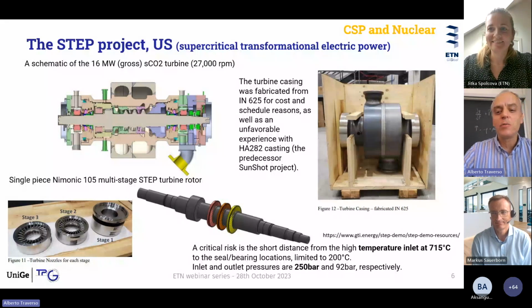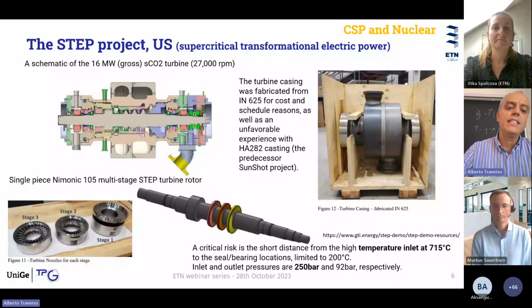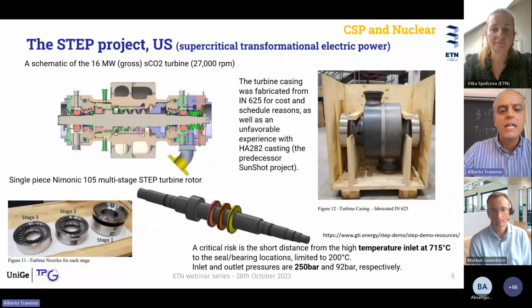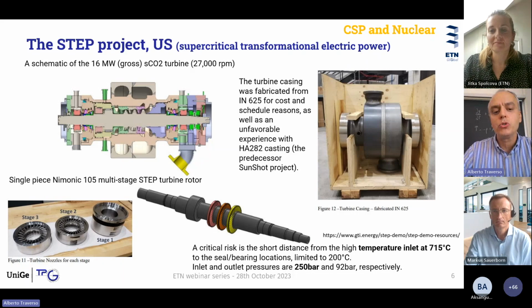Okay, so the STEP project is probably the most prominent one, and is targeting a 10 megawatt net power, but the turbine is actually 16 megawatt. And this comes from the Sunshot program targeting CSP application. If we look at the turbine itself, we find some features that are common also to other turbines, which has a quite cylindrical shape of the whole shaft. And this poses challenges in terms of thermal management. This was one of the questions of the audience: thermal management of the hub itself, as well as ventilation losses that may occur due to the too small size of the blades.